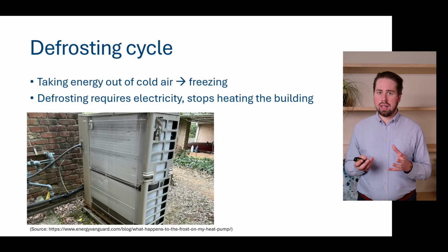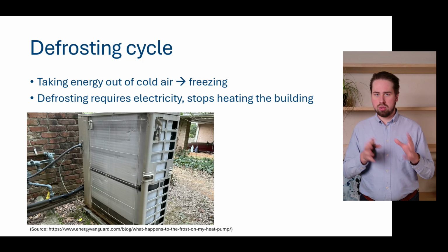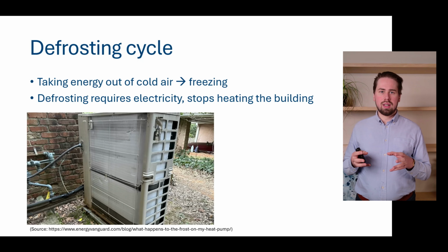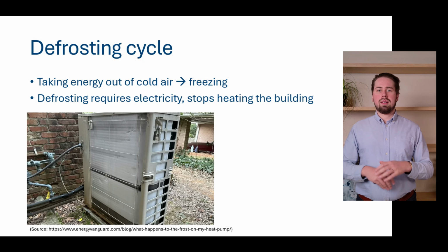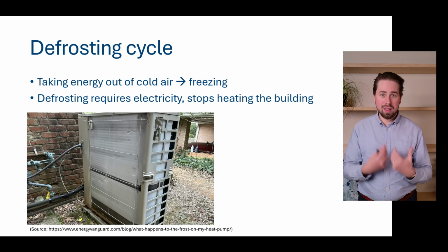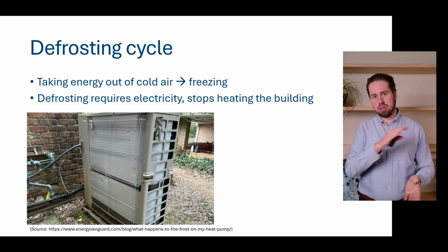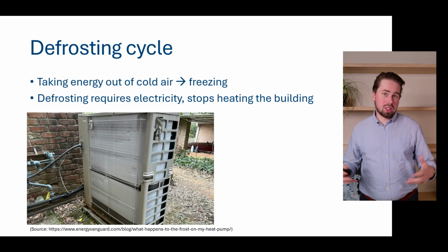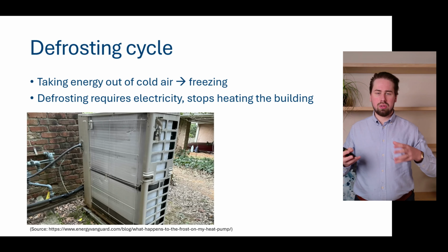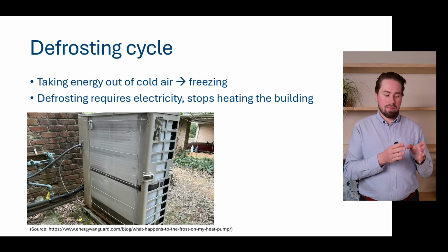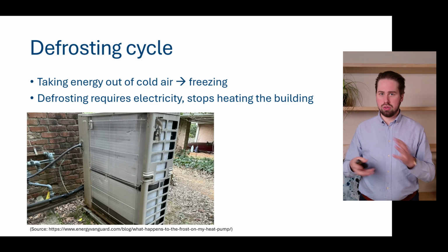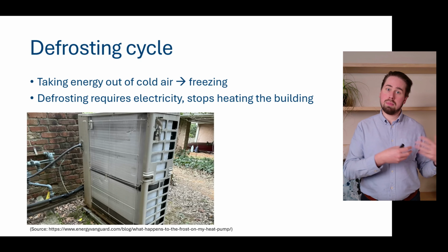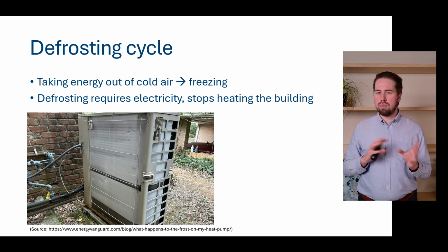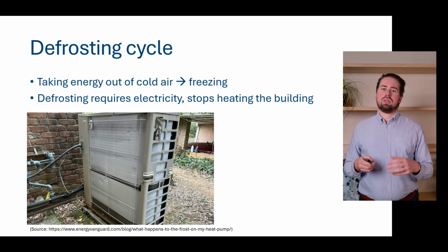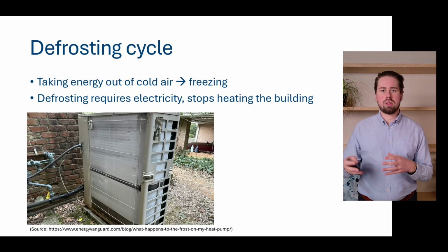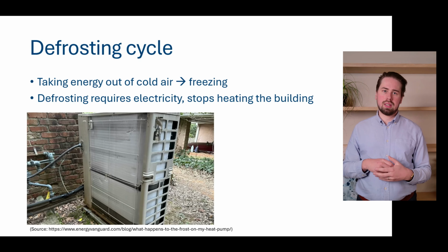So this defrosting cycle consumes electricity, but the other problem is that when it's defrosting itself, it cannot deliver heat to the building. And when you have a big building and quite a lot of heating demand, and these heat pumps shut down in order to defrost themselves, it's possible that you need to install extra capacity in order to be sure that your peak demand is met. Because if your heat pumps are turning off in order to defrost themselves, perhaps your comfort levels are not met. So that's always something to keep in mind in cold seasons: that your peak heating demand can actually be met with your air source heat pumps as well, taking into account these defrosting cycles.